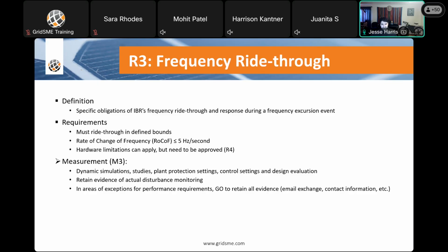Very similar measurements, dynamic simulation studies, plant protection settings, etc. Retain evidence of your actual disturbance monitoring. Again, any frequency disturbances that happen on the grid, if they come in and do an audit, they're going to want to see that you were recording the data during that event. And in areas of exceptions for performance requirements, GO to retain all evidence.